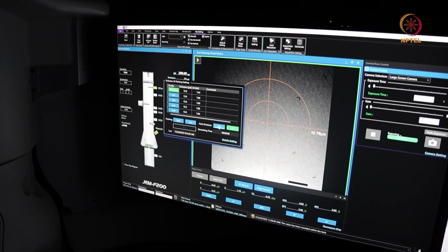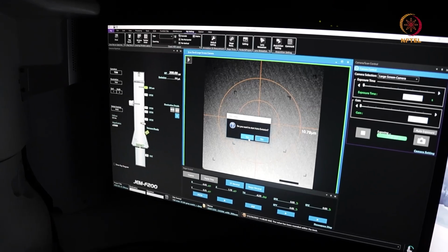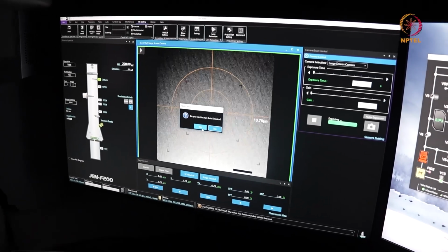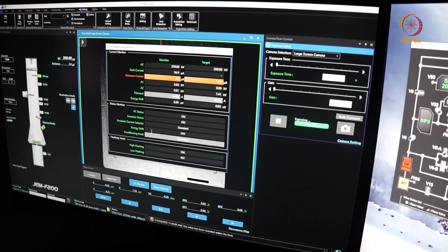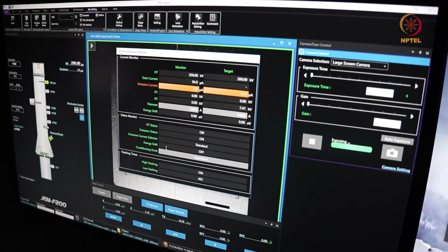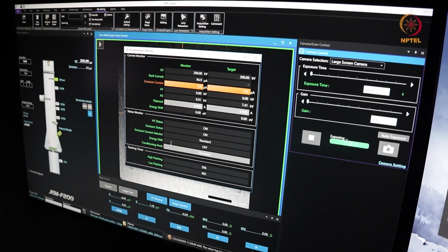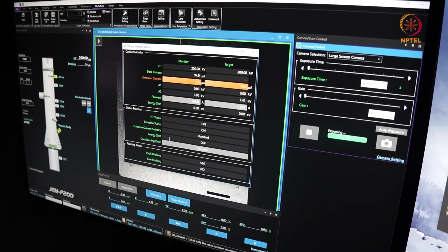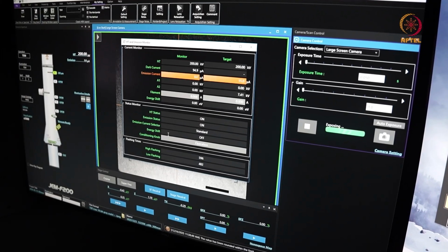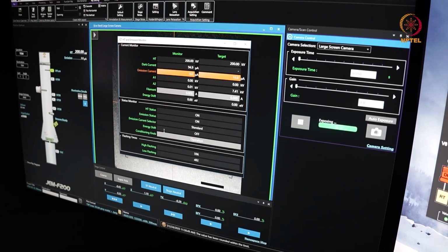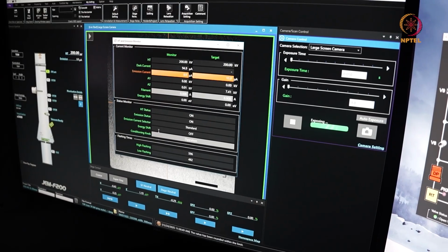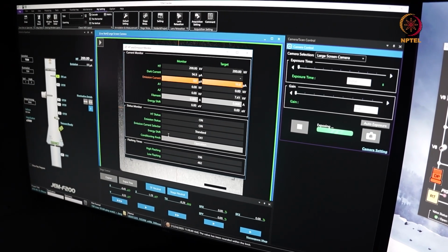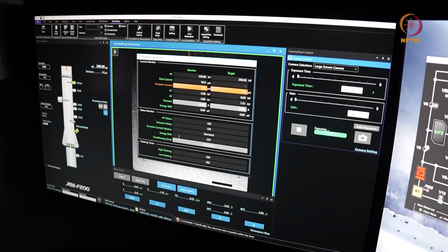And I'll just switch on the emission by doing this auto emission on, and you get this window. Do you want to start auto emission? Yes. And what you see here is you have two lenses, the A1 and A2 lens in the gun, and first by turning on the A1, you will see that the emission current starts going up, and once the emission current stabilizes, you want to sustain it at a preset value of around 7.41 kilovolt, and you maintain 15 microamp emission. After the emission is on, you switch on the beam or open the column valves by pressing this button.